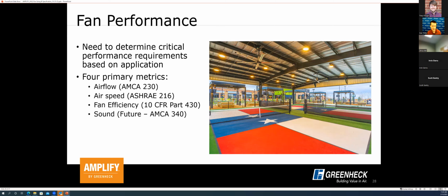And then sound, last but not least, AMCA 340 is a standard currently in development. It's not actually used at this point to measure or catalog sound data, but in the future, when that standard is finalized and published, there will be a standard test procedure and certification program available for HVLS sound. So the big takeaway is there's only one certification program available today, which is for airflow. All the rest of these are standards that should be used by a manufacturer to provide you data that is repeatable and comparable.